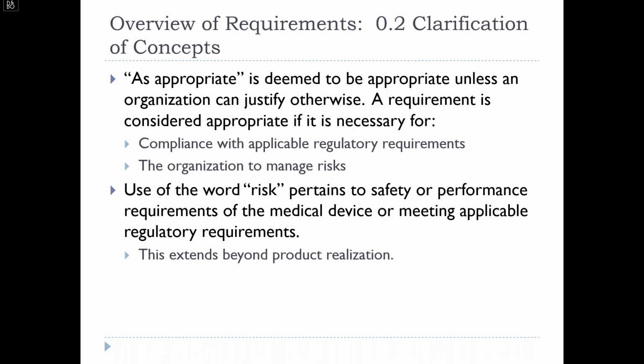And use of the word risk pertains to the safety or performance requirements of the medical device or meeting applicable regulatory requirements. So this is going to extend beyond product realization. If sterilization needs to be maintained, obviously throughout distribution, that's well beyond product realization.